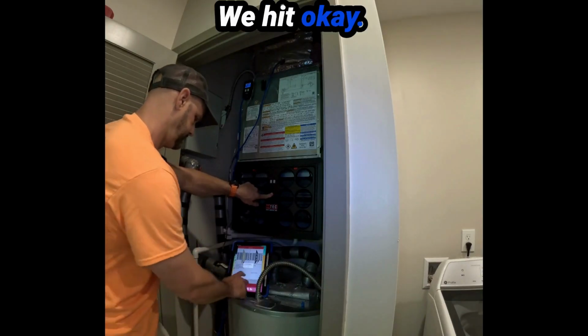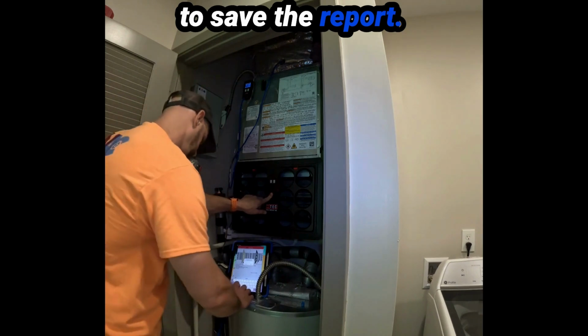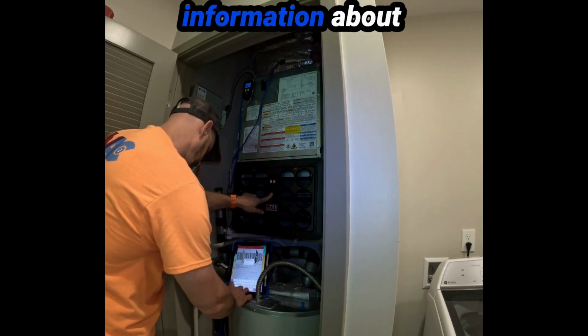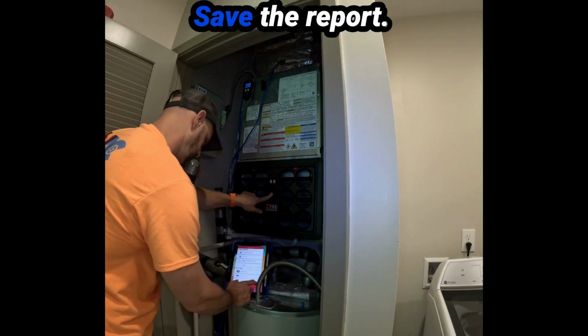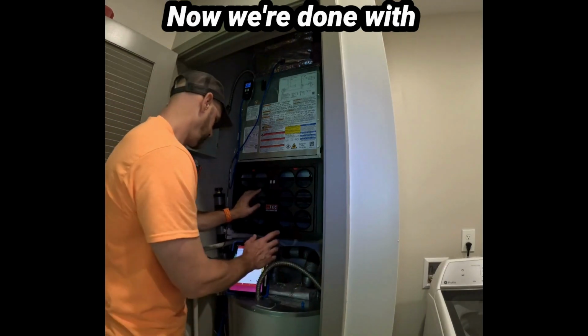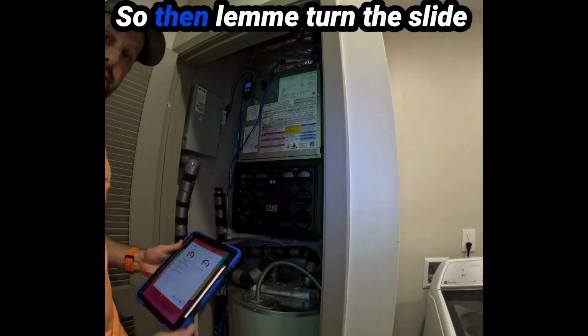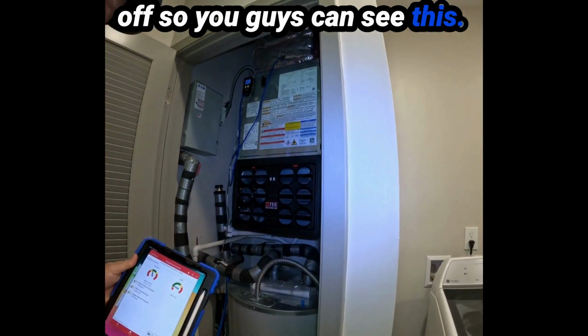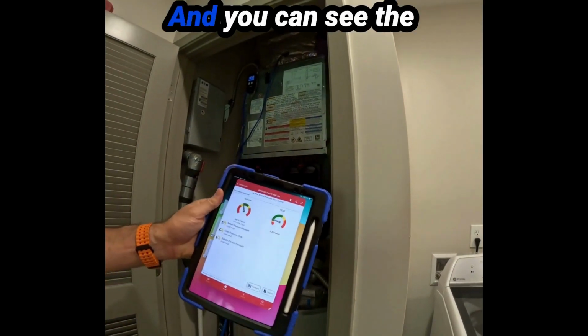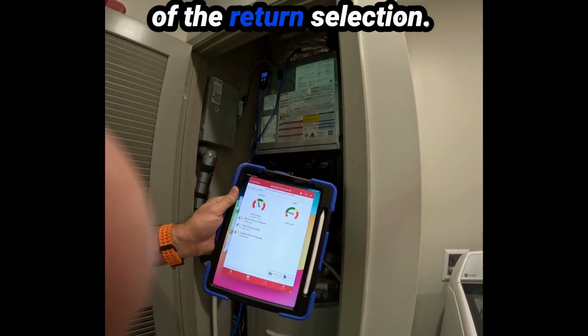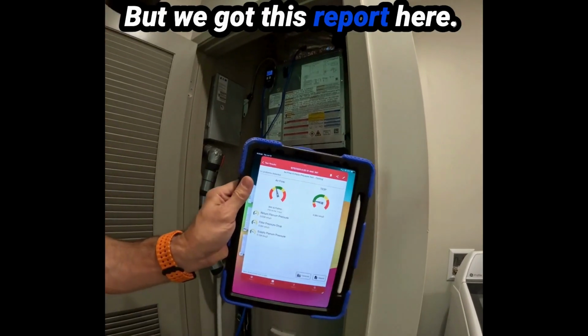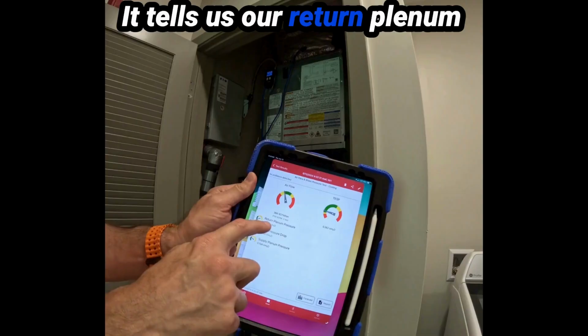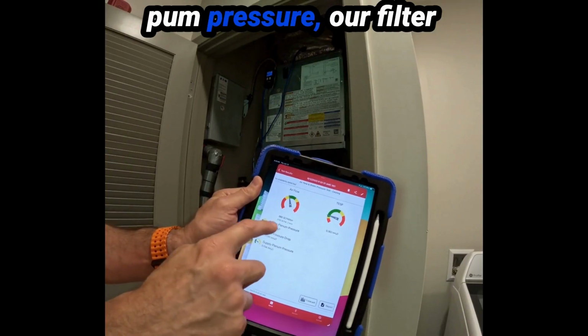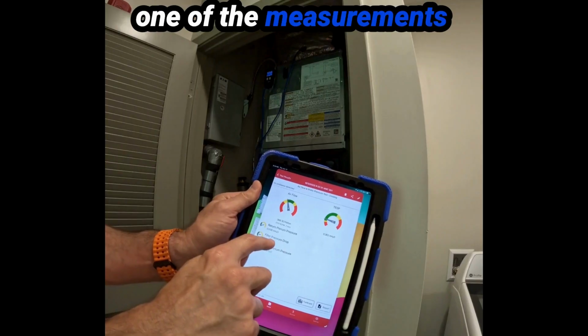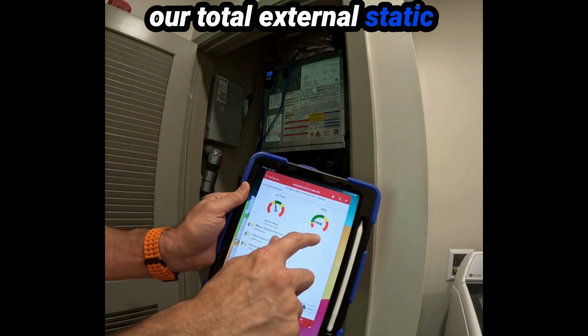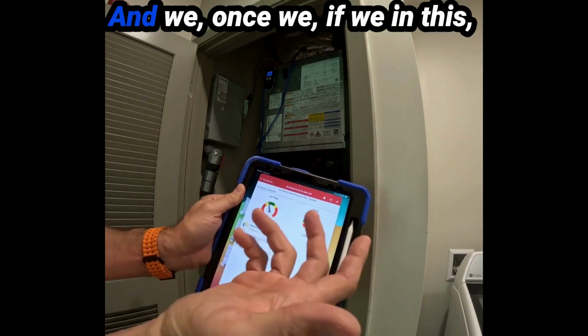We hit OK, and then it wants us to save the report. So put in some quick information about where we're at here. Save the report. Now, we're done with that part of the test. So then, turn the slide off so you guys can see this. You can see the TrueFlow is staying there on its own because of the return suction. But we got this report here. It tells us our return plenum pressure, our supply plenum pressure, our filter pressure drop, which is one of the measurements that we need for TAB, and our total external static pressure, which we also need.